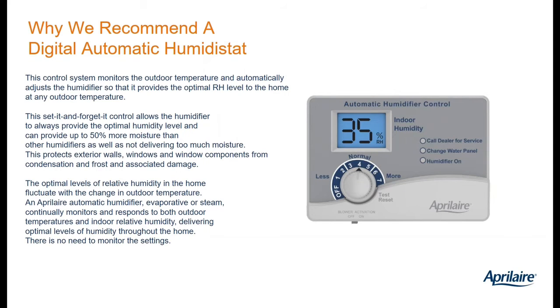If the goal during the heating season is to raise the humidity up as high as we can without getting damaging condensation, what we're really saying is we want to be able to track the RH set point to the outdoor temperature. And if we use the automatic humidistat, it comes with an outdoor temperature sensor. So it knows what the outside temperature is. So what does that mean to you? It means overnight, as it gets colder and colder and colder, the automatic humidistat is automatically going to lower the RH set point without you having to do anything. The following morning, as it gets milder and milder outside, the humidistat will automatically raise the RH set point. So you get the benefits of being able to hold a little bit more humidity in the home.